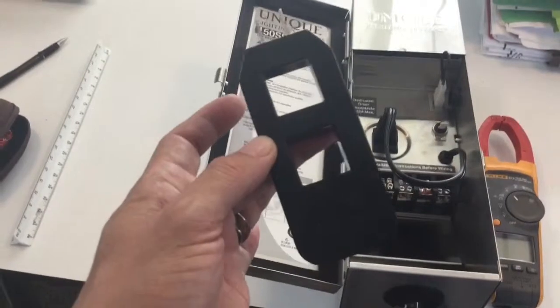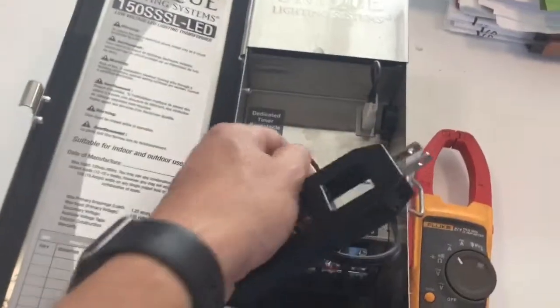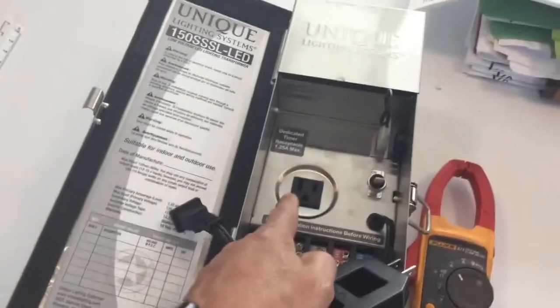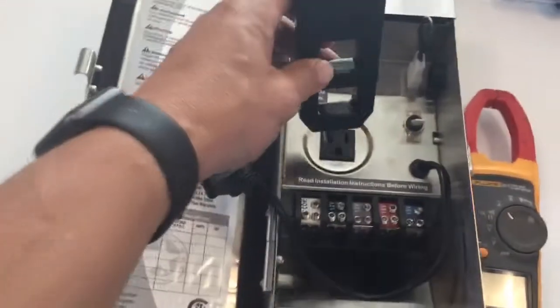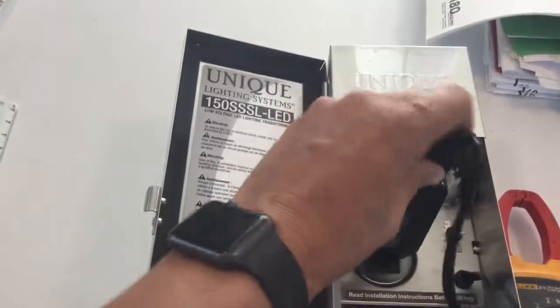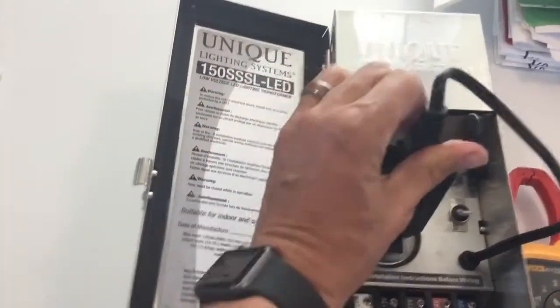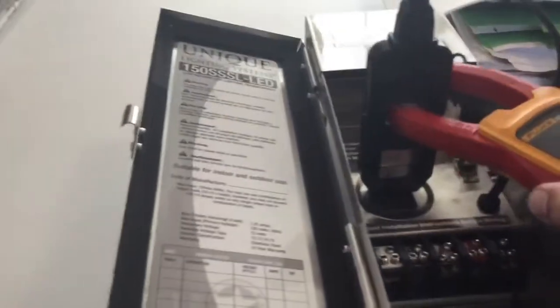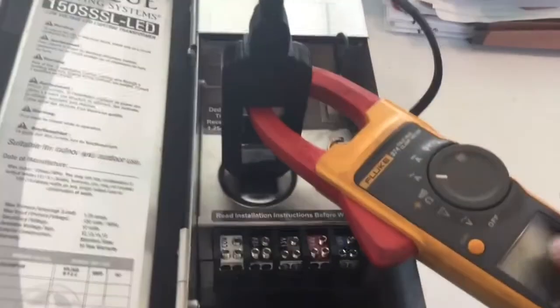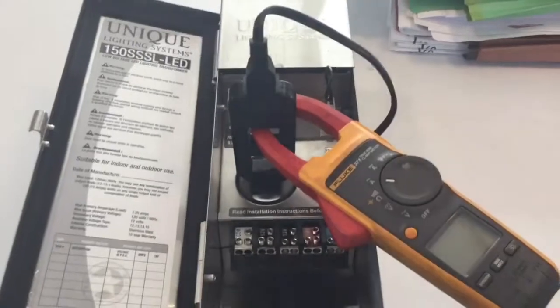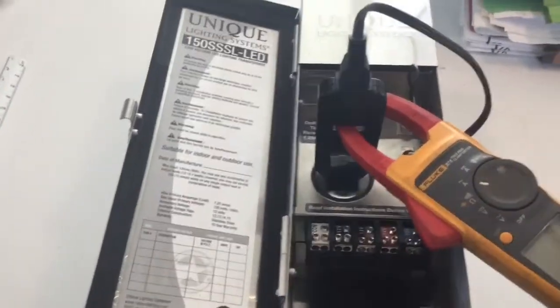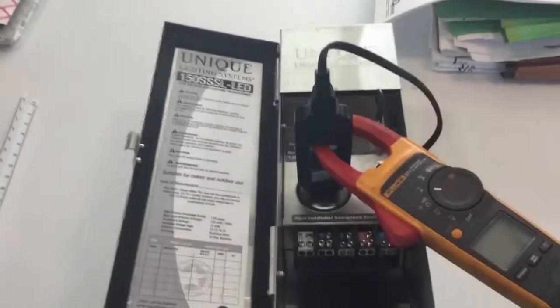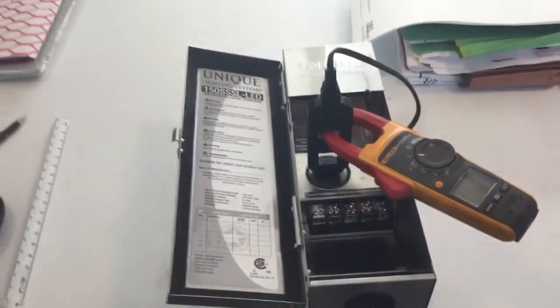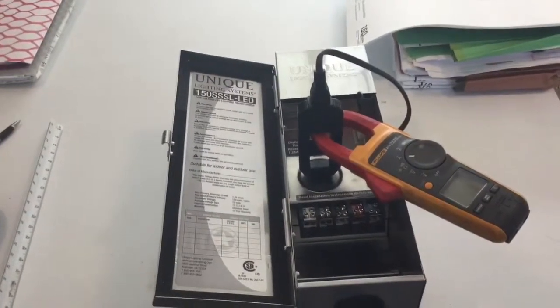So if you've got one of these, and you've got a transformer you need to test, what you need to do is unplug this plug inside the transformer. Usually that's where the timer is plugged in, so get rid of that as well if there's a timer in there. And then plug this in that location, plug your transformer right into the top of that, and now you have the ability to go back to your amp probe and circle around one of those, and it'll give you your reading. That's the best way to do it. And again, if you're at 0.5, 0.75 on a 1.25 transformer, you're doing great. If you're getting close, now you're running into trouble. So those are the 3 ways to test a transformer for its capacity.